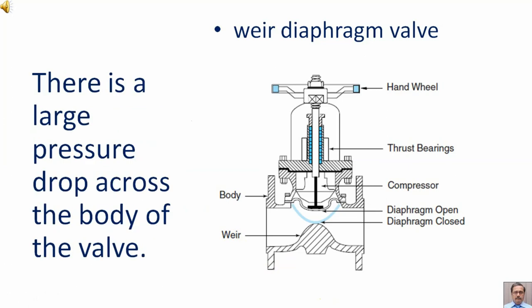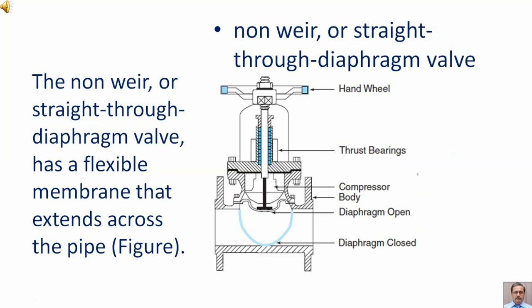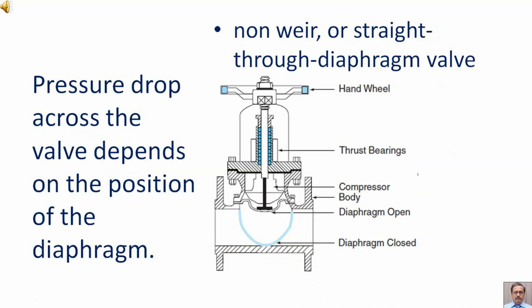There is a large pressure drop across the body of the weir valve, and it uses thick, durable diaphragm materials. The non-weir, or straight-through, diaphragm valve has a flexible membrane that extends across the pipe. The pressure drop across this valve depends on the position of the valve.